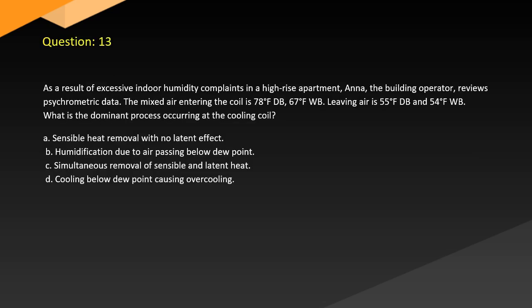Question 13. As a result of excessive indoor humidity complaints in a high-rise apartment building, the building operator reviews psychrometric data. The mixed air entering the coil is 78 dry bulb, 67 wet bulb, leaving air is 55 dry bulb and 54 wet bulb. What is the dominant process occurring at the cooling coil? A. Sensible heat removal with no latent effect. B. Humidification due to air passing below dew point. C. Simultaneous removal of sensible and latent heat. D. Cooling below dew point causing overcooling.